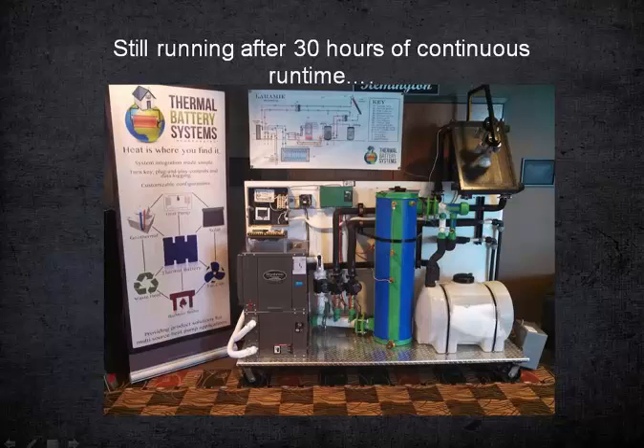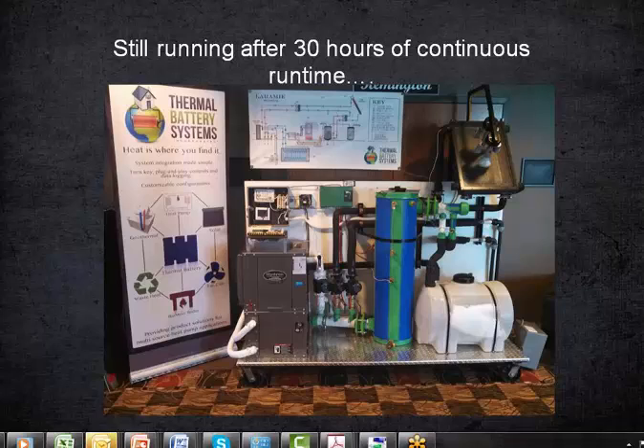The 3 pumps you see: one is for the heat pump from the transfer tank. To the far right you'll see a single ground loop, which this was built to kind of mimic the system in Laramie. And the other pump is to the solar collectors, which uses that transfer tank as a drain back tank. It can also be adapted. The actual Laramie project does have heat exchangers and such in place, and my particular system has a drain back tank with a heat exchanger, so it's piped a little bit differently than this. But ambient energy was more than anything what was keeping that going. You can see the frost on the thermal battery, and of course how cold it was going into that little 12,000 BTU heat pump. But the transfer tank was sweating.